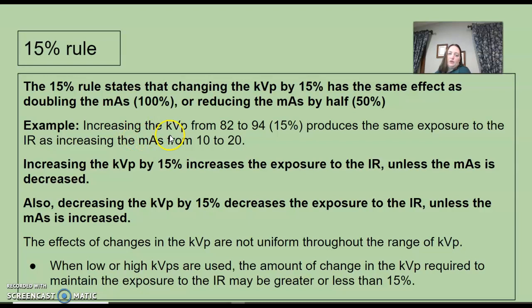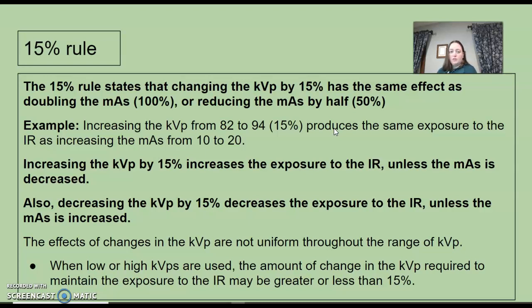Here's an example. If you increase the KVP from 82 to 94, which is a 15% increase, that will produce the same exposure to the image receptor as if you increase the mAs from 10 to 20 — as if you doubled the mAs. So increasing the KVP by 15% increases the exposure to the IR unless you decrease the mAs to counteract it.